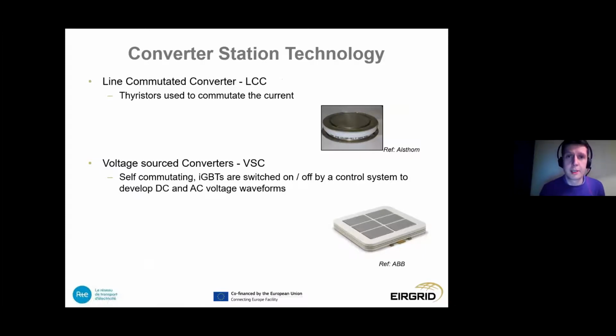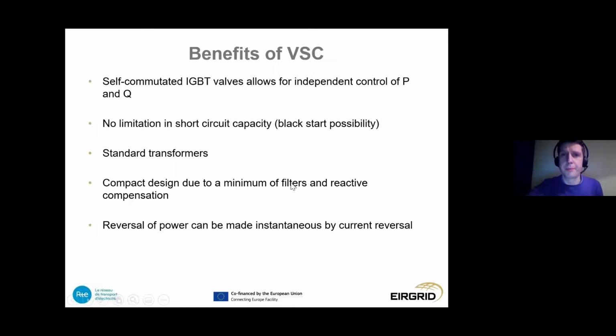You have line commutated converters, where thyristors are used to commutate the current. And we have voltage source converters, which we're going to implement for the Celtic link, which are self-commutating, using IGBTs as switches. These are switched on and off by a control system to enable the development of the DC and AC voltage waveforms. The IGBT valves in VSCs allow for independent control of active and reactive power. There's no limitation in terms of short circuit capacity, and this allows black start functionality.